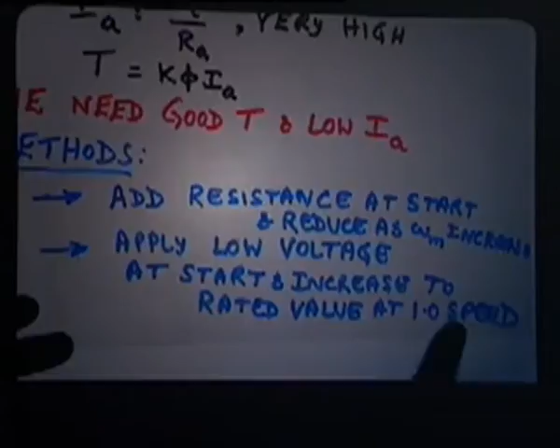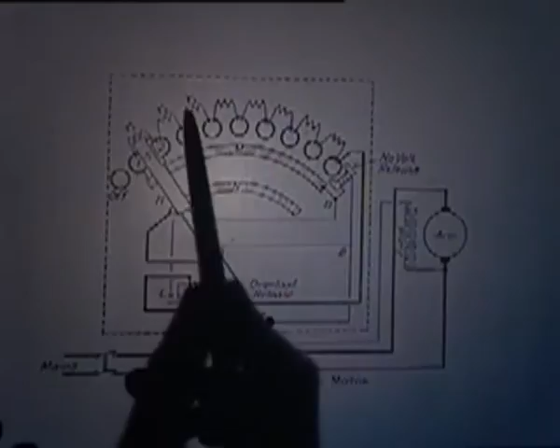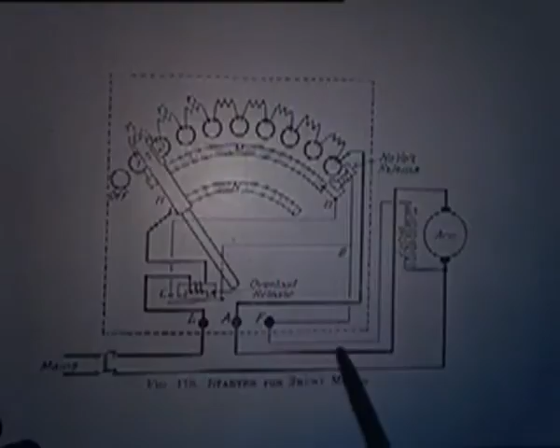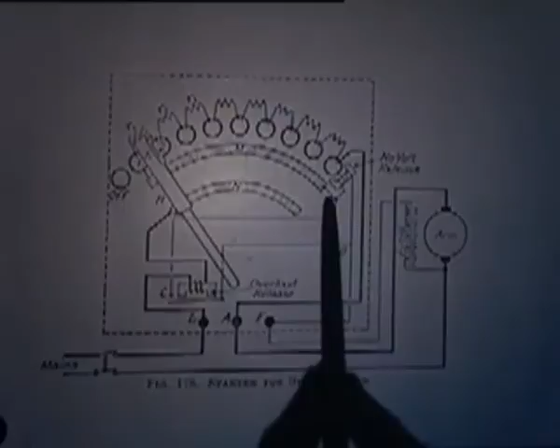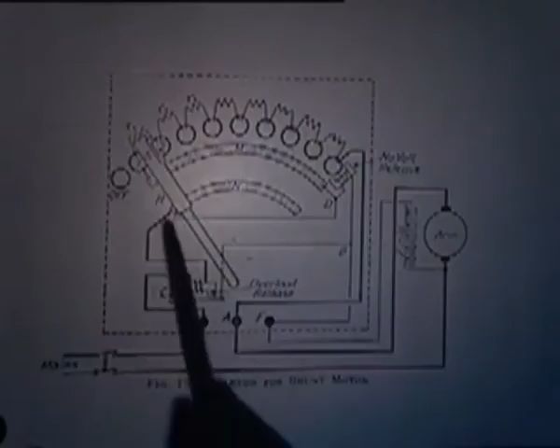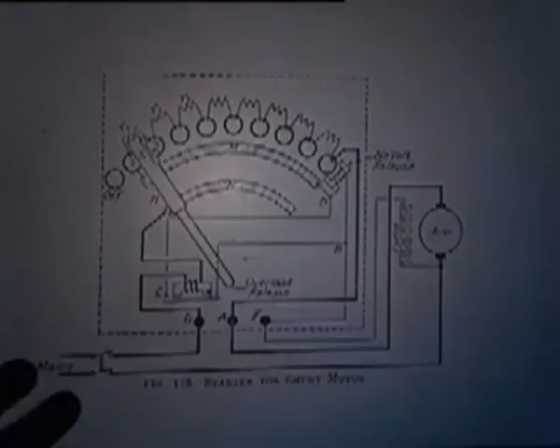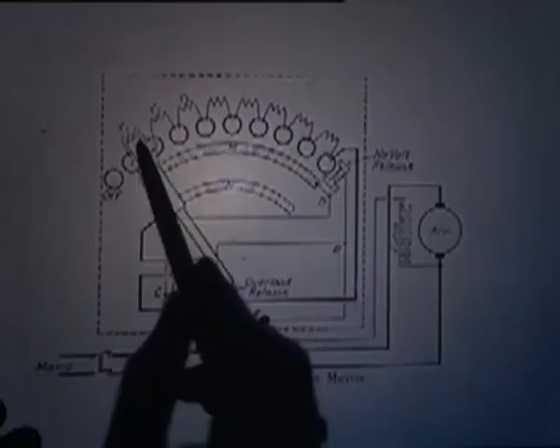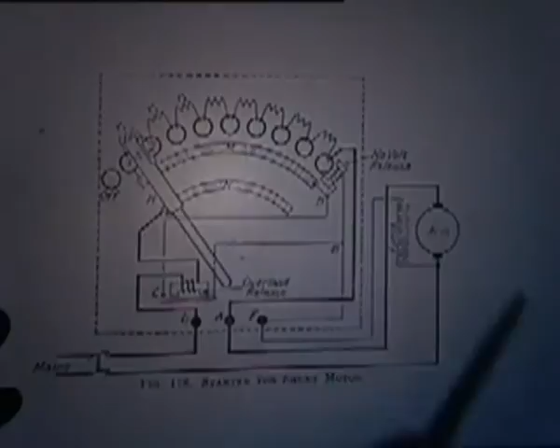Now here is a typical diagram of a starter. This is a starter for a shunt motor. These are the elements R1, R2, R3 and so on connected to the DC shunt motor, where the field is connected fully to the supply. It has some internal protection schemes. Originally this handle will be in the off position, and if you want to start the motor, you have to slowly move it in this way. Initially all the resistance will come into the picture, then you slowly cut off the resistances, and finally you come to this position. The final running position is when the handle is in this position, and as it comes to this position, there is an electromagnet here which will attract this iron piece and hold it in this position. When it is held in this position, the motor will continue to run.